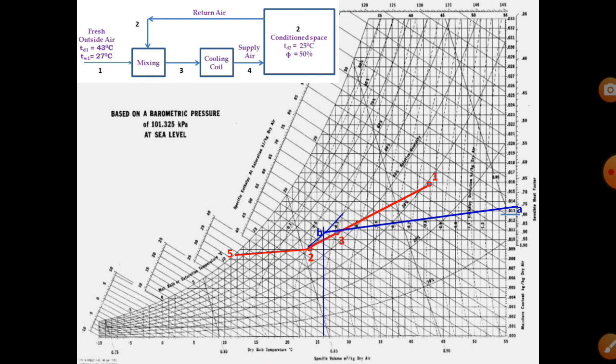Where the saturation curve intersects, mark point 5 — this line represents the RSHF (Room Sensible Heat Factor) line. From point 3, draw one more line to the saturation curve to reach the apparatus dew point temperature — the cooling coil temperature (TD6). Point 3 is the entry to the cooling coil. The coil temperature is not directly given, but the bypass factor is 0.2, so we use the trial and error method with the bypass factor formula.